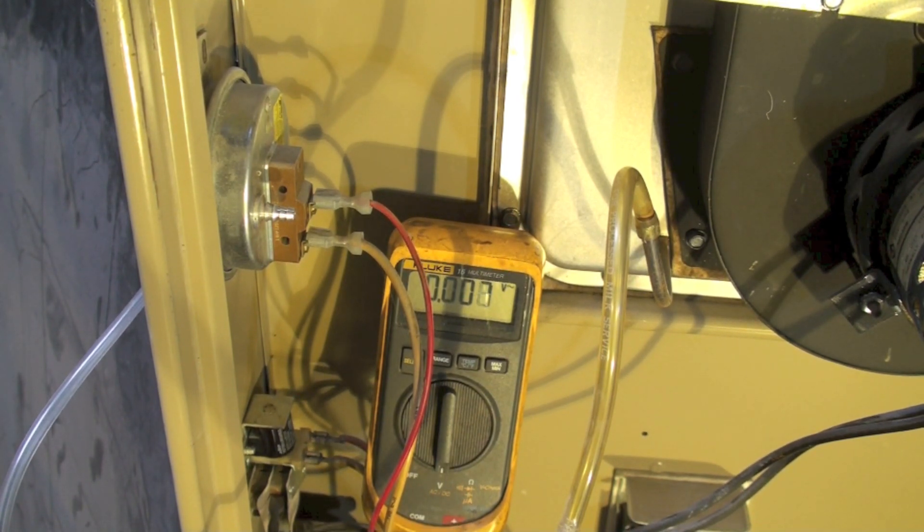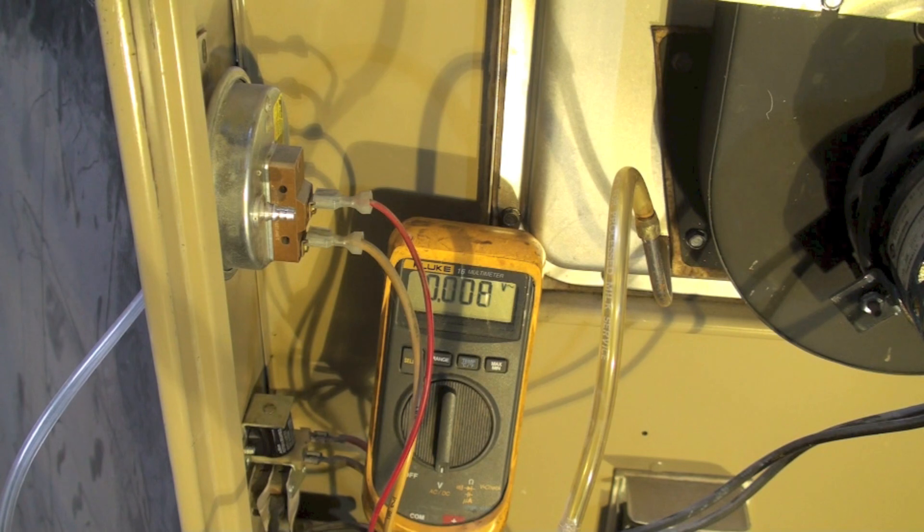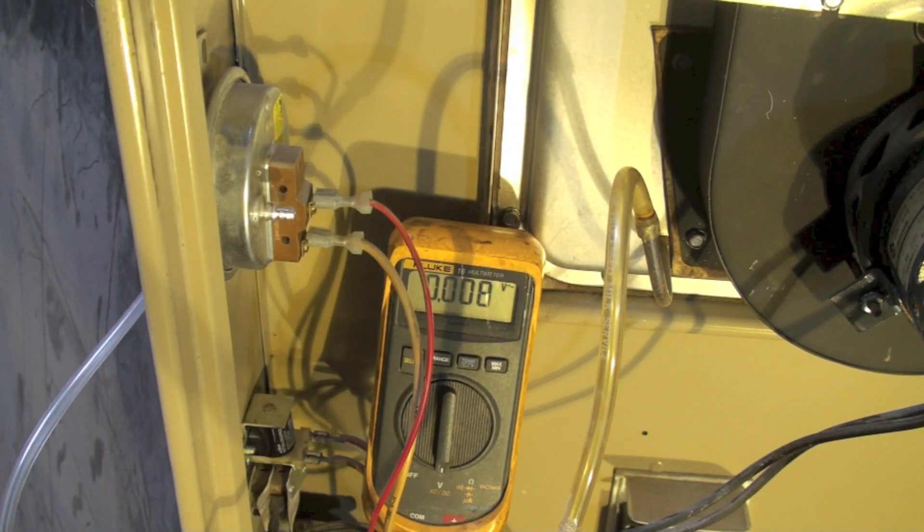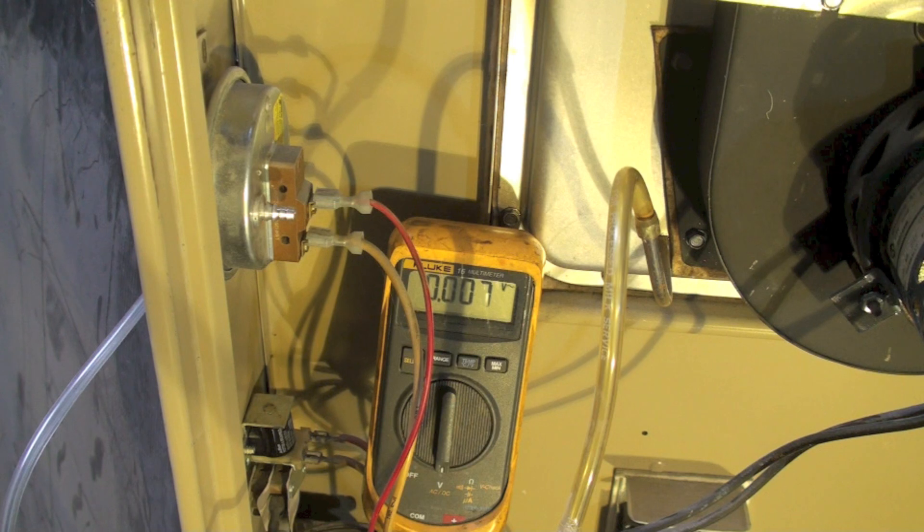I have a problem other than the pressure switch that's causing this. First, I'll probably clear this tube out, maybe pull the inducer off and take a look at it, see what condition it's in, remove the vent, see if it works with the vent removed, that sort of stuff. Those are pressure switch problems in this thing.